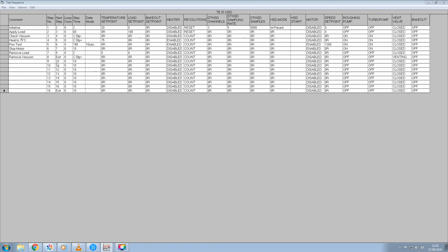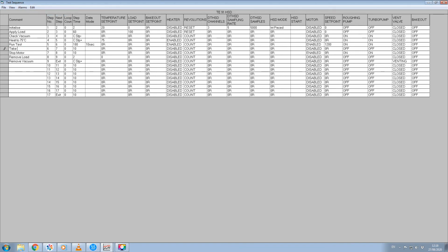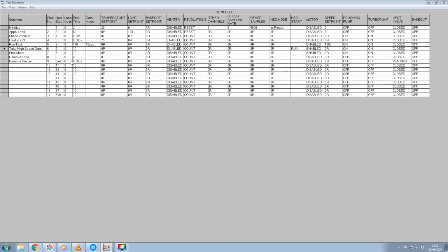To trigger high-speed data acquisition at various points in the test, we can program a loop. We start by adding a step during which high-speed data acquisition is triggered. In this example, I will amend step 4 to run for 170 seconds with the new step, step 5, during which high-speed data acquisition will be triggered, lasting for 10 seconds.